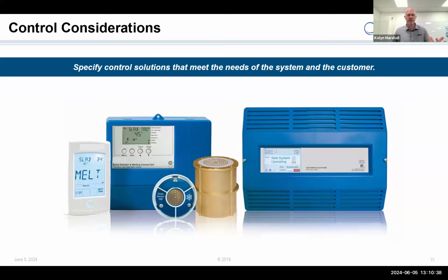And you're like, well, why would you ever need a retrofit? Well, ironically, sometimes the slab gets poured and they forgot to put in the sensor. It happens. Miscommunication. The snow melting guy, the electrical guy didn't talk to the concrete guy, and suddenly the concrete's poured and there's no sensor. So you can retrofit and use a pole mount as well.